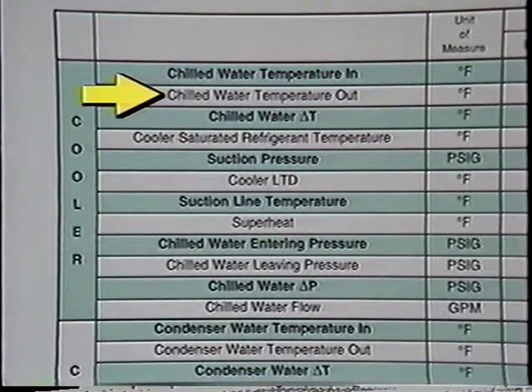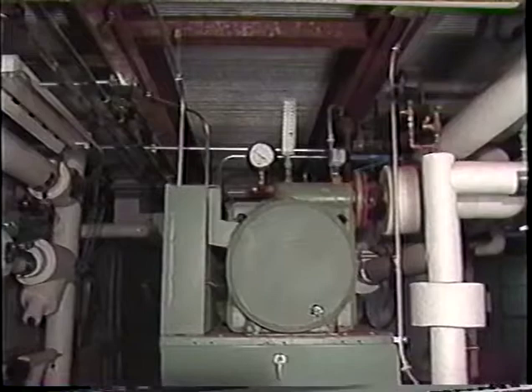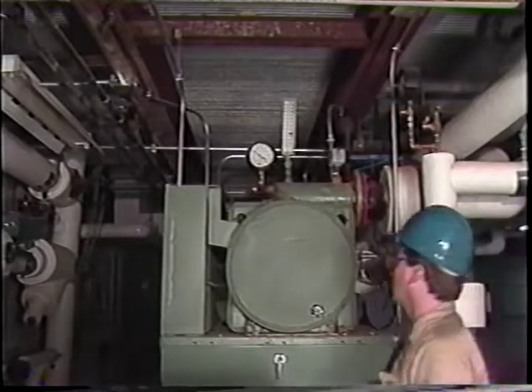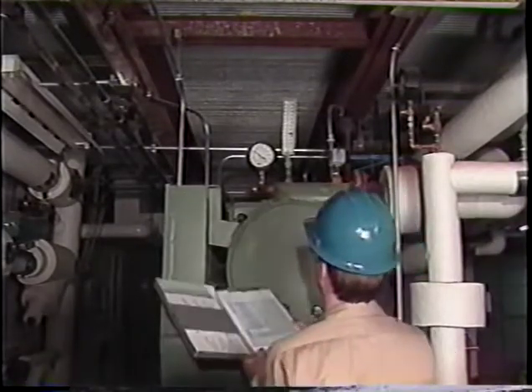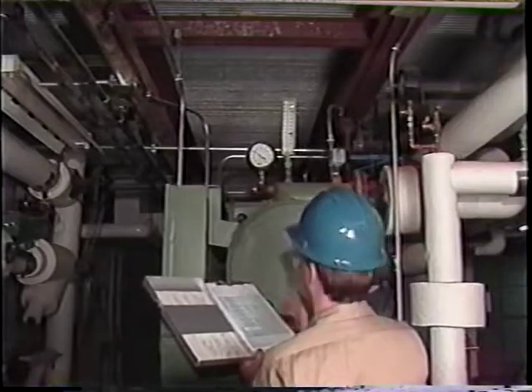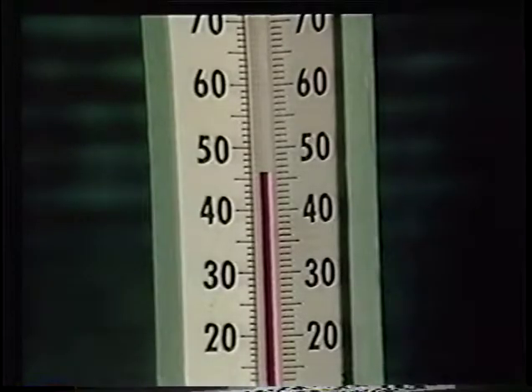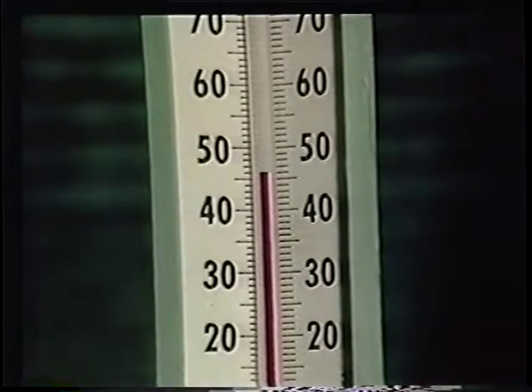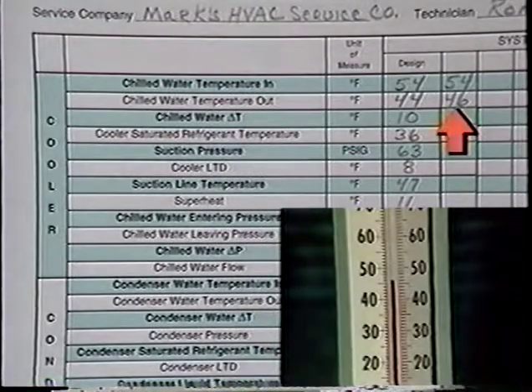Chilled water temperature leaving the cooler. We also need to record the chilled water temperature leaving the cooler. After the chiller is placed in operation, this temperature should be within plus or minus 1 degree Fahrenheit of the design leaving water temperature at full or part load conditions. Design leaving water temperature at full load is typically 44 degrees Fahrenheit.